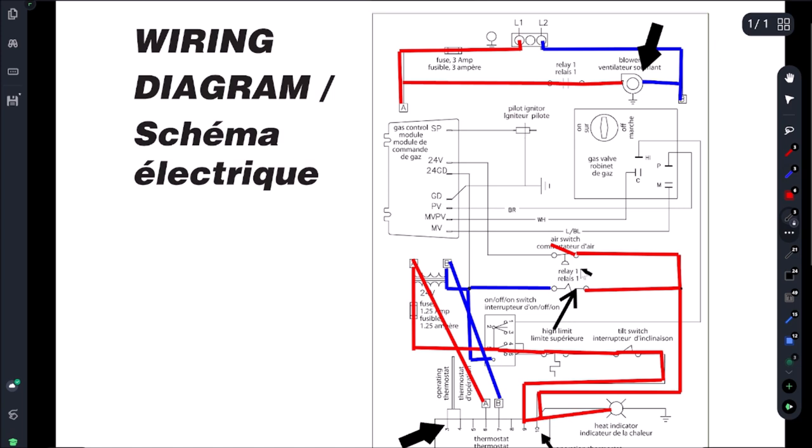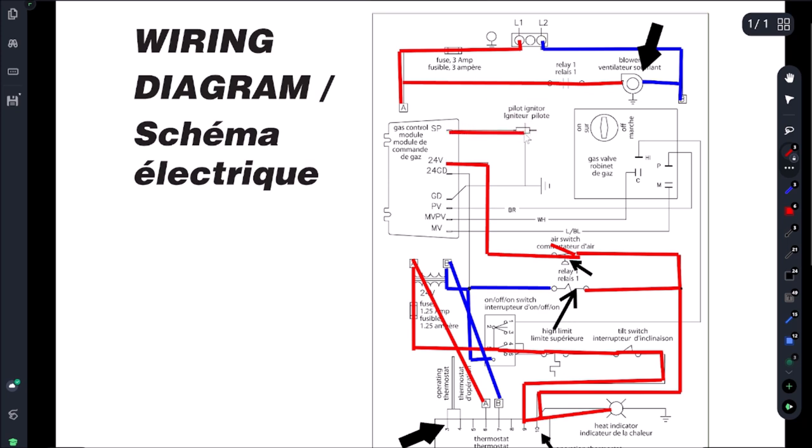Why? Because we need this combustion air switch to be closed. Once that completes we're going to come up here to our 24 volts, and then once we get power at this 24 volts we're going to get our igniter and then we're going to send power to the gas valve.